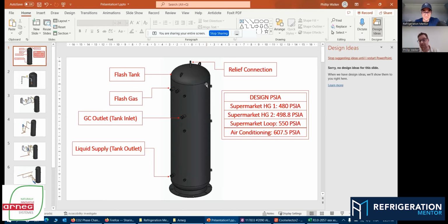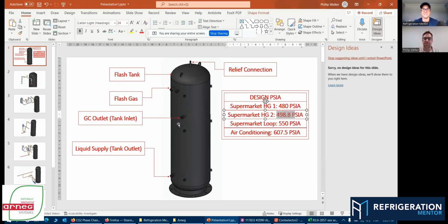Absolutely, because think of the temperature running out here. The days of 98 degrees are kind of out the window. That's out over here coming down from the gas cooler. We're flashing that down, just like you would with any type of DX system. It's running in here. If we're at 500 pounds, the temperature in here is 32 degrees. We've got 32-degree liquid. Yeah, that's so cool. It's cold.